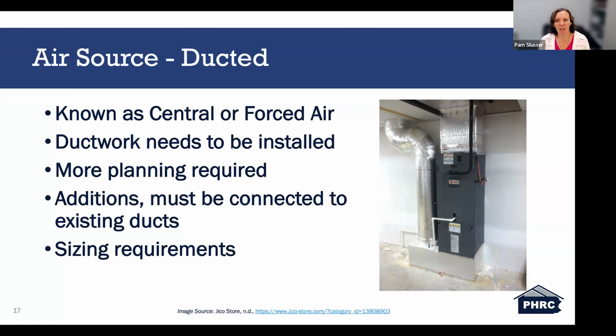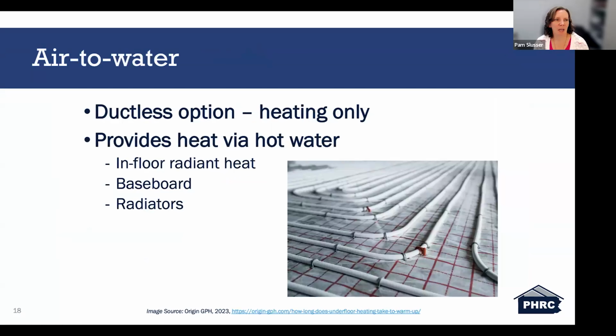When you're adding an addition onto the home, there's planning that needs to take place to connect installed ductwork, which is very, very important. Sizing for these systems is essential, especially for the ducts, to be sure the proper volume of air is being moved to properly heat as well as cool the home. And then we move on to the air to water system. This is a less common but highly effective heat pump option.